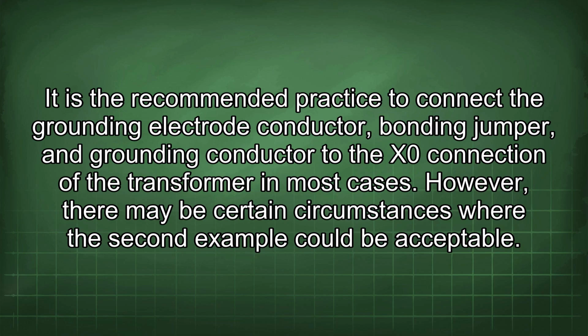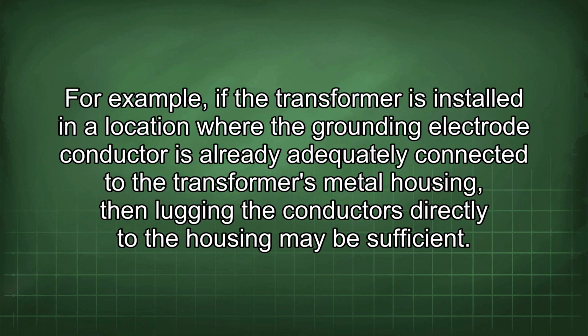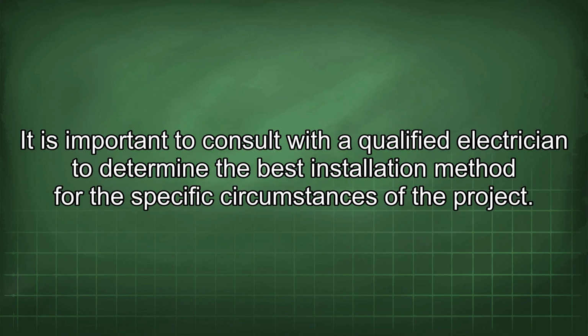However, there may be certain circumstances where the second example could be acceptable. For example, if the transformer is installed in a location where the grounding electrode conductor is already adequately connected to the transformer's metal housing, then lugging the conductors directly to the housing may be sufficient. It is important to consult with a qualified electrician to determine the best installation method for the specific circumstances of the project.